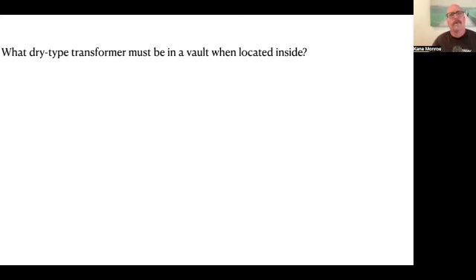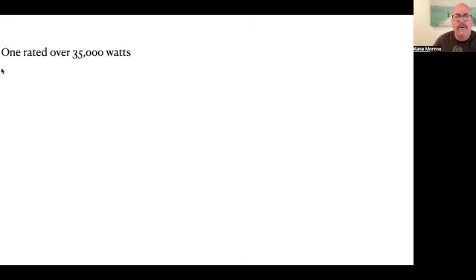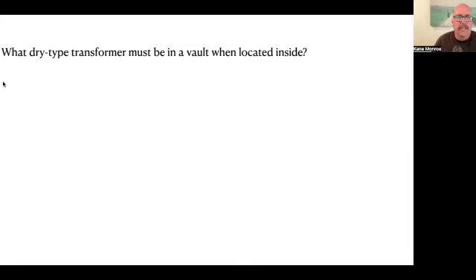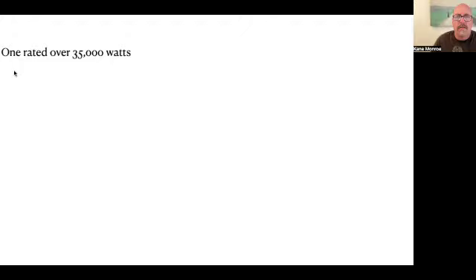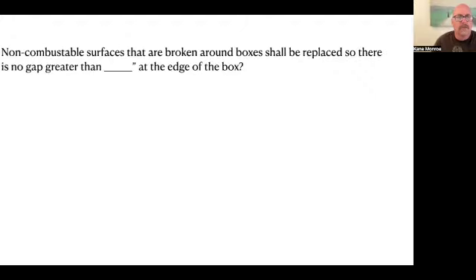Next question. What dry type transformer must be in a vault when located inside? So what type of transformer? One rated over 35,000 watts. 35,000 watts. So be on the lookout for that one. Again, what dry type transformer must be in a vault when located inside? So inside the vault, one rated over 35,000 watts. Cool, let's go to the next one.